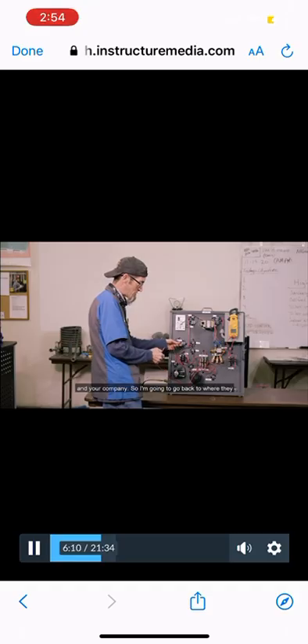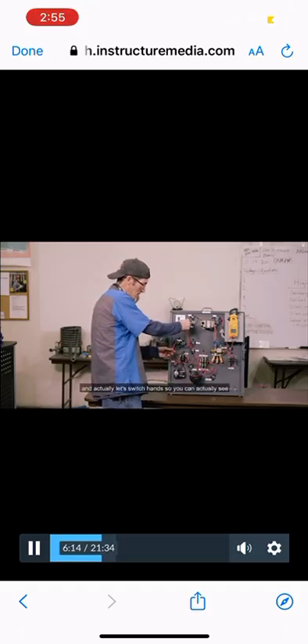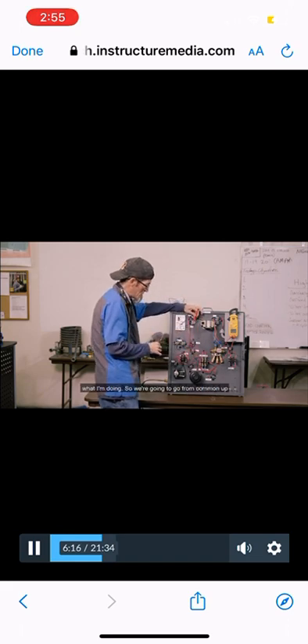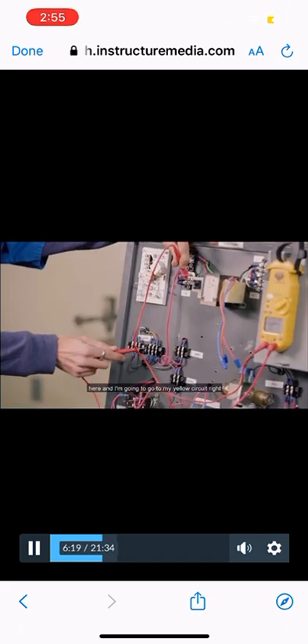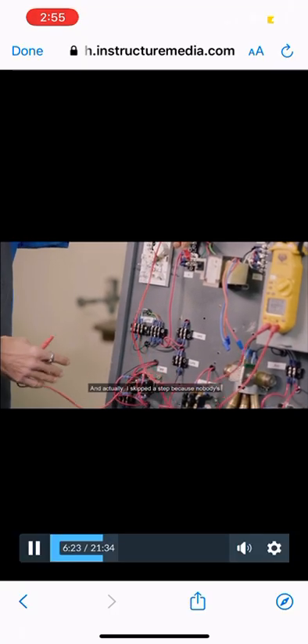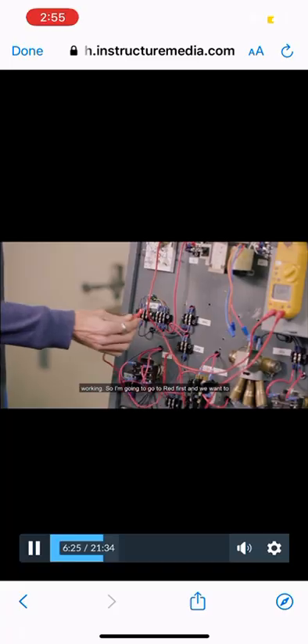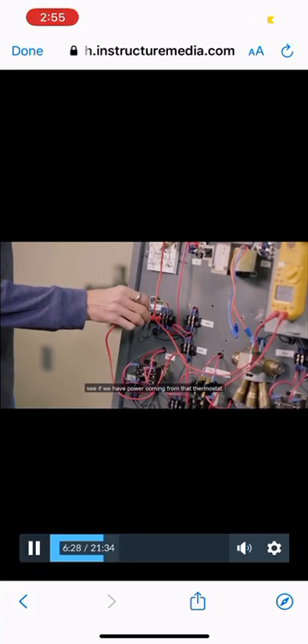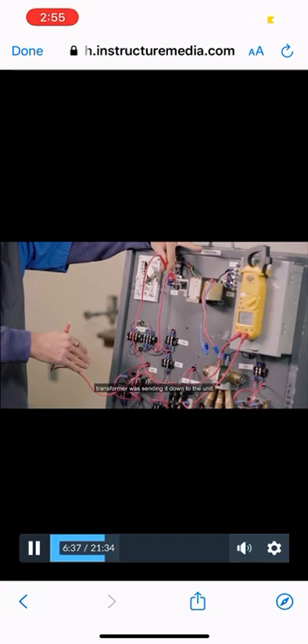So I'm going to go back to where they come into that unit. I'm going to go from my common up here, and actually let's switch hands so you can see what I'm doing. We're going to go from common up here, and I'm going to go to my yellow circuit right here, because that's what's going to tell what to do. And actually I skipped a step because nobody's working, so I'm going to go to red first. We want to see if we have power coming from that thermostat. And I don't. Unlike the first problem, where we had power on this wire, which told us that the transformer was sending it down to the unit, in this particular problem I don't have anything coming into my unit right now.